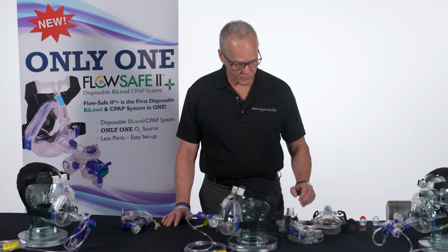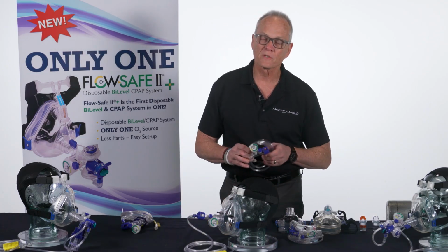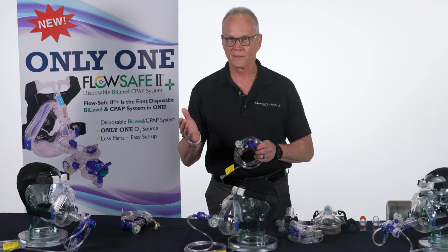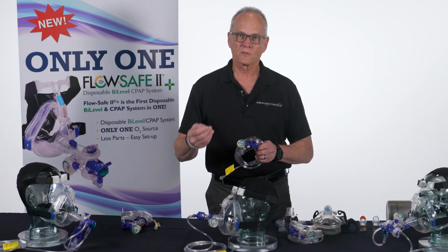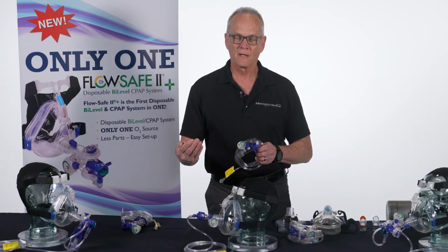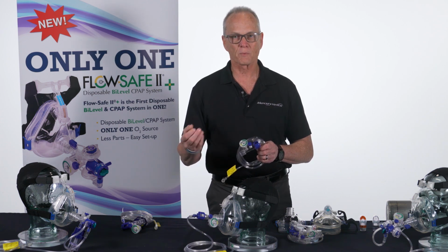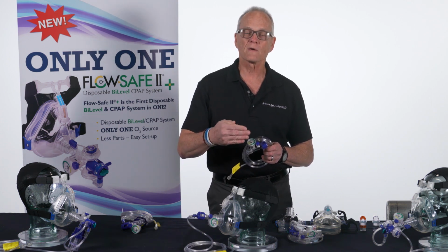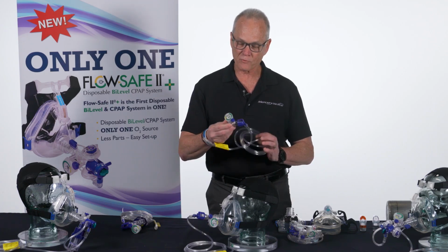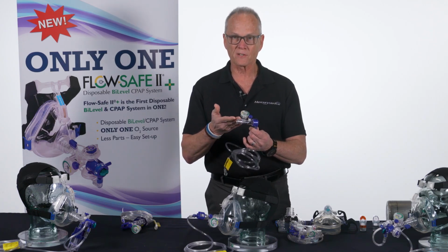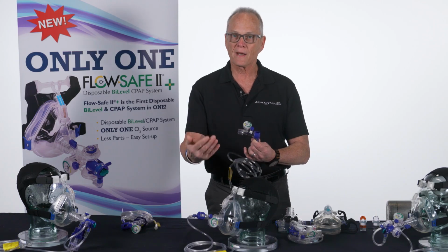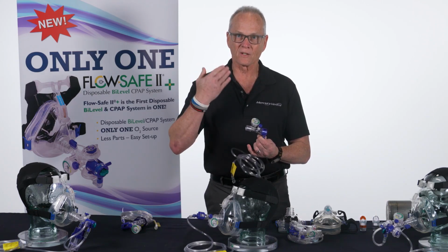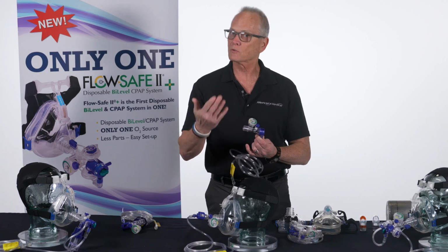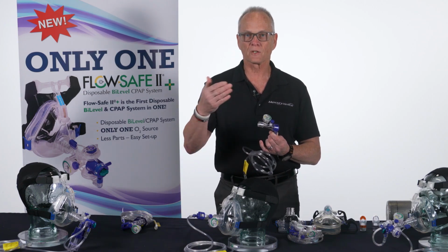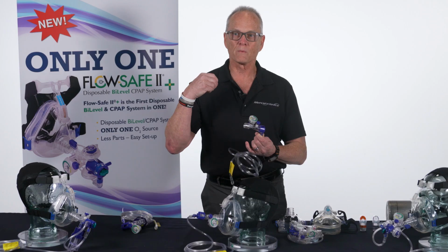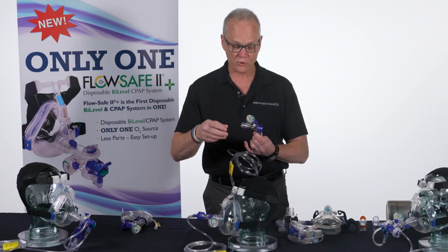Now, all of our FlowSafe products, and this is an example of a FlowSafe 2, have some things in common. How they create the pressure is by attaching to a flow meter or regulator, using the gas flow to create the pressure, whether it's an inspiratory pressure or even the resistance. As the gas comes through the oxygen tubing and through the device, it creates a pressure that helps a little bit on the inhalation side of the respiratory cycle, and it also creates the resistance giving you the exhalation pressure, almost like an EPAP, which I'll explain shortly.